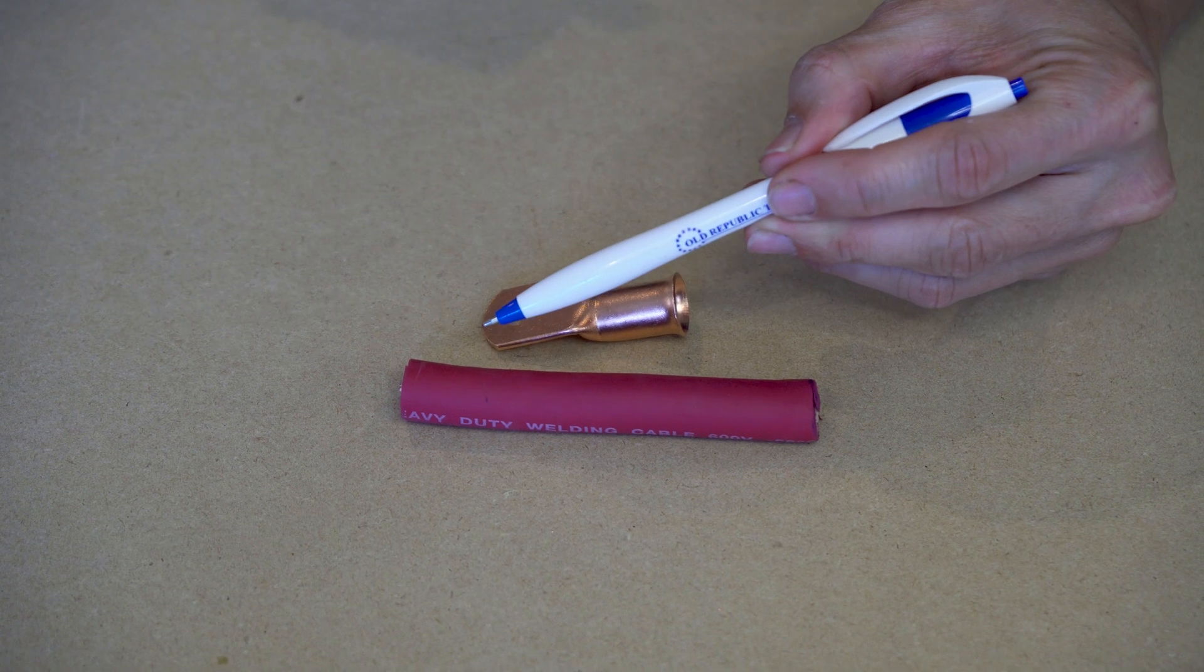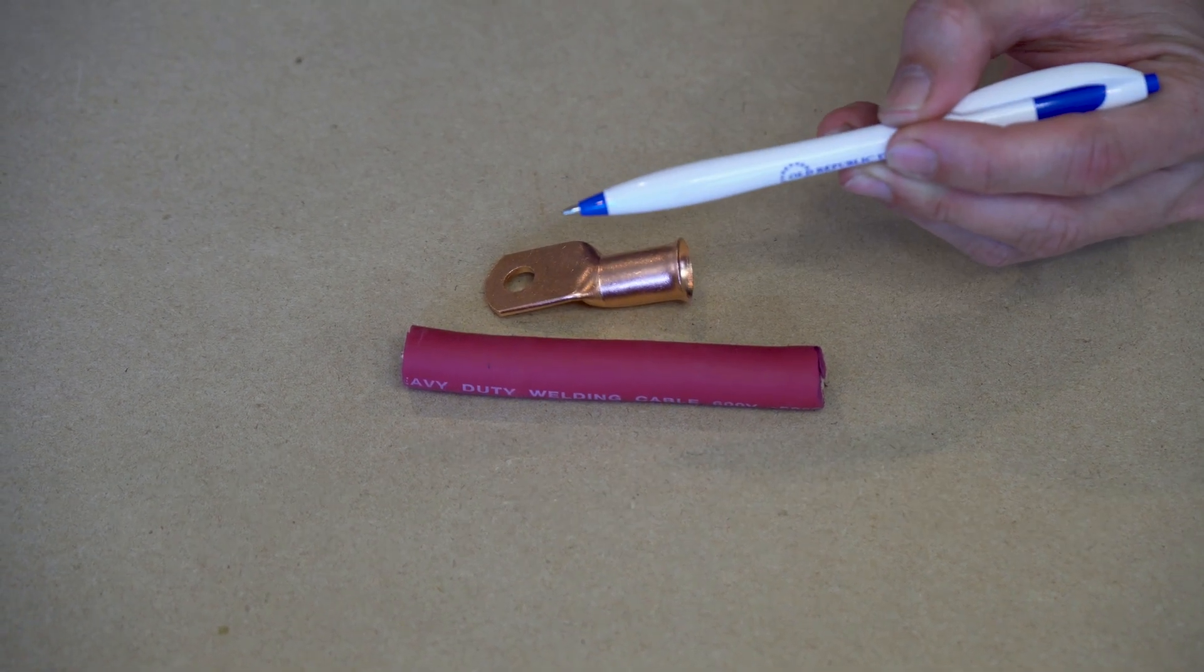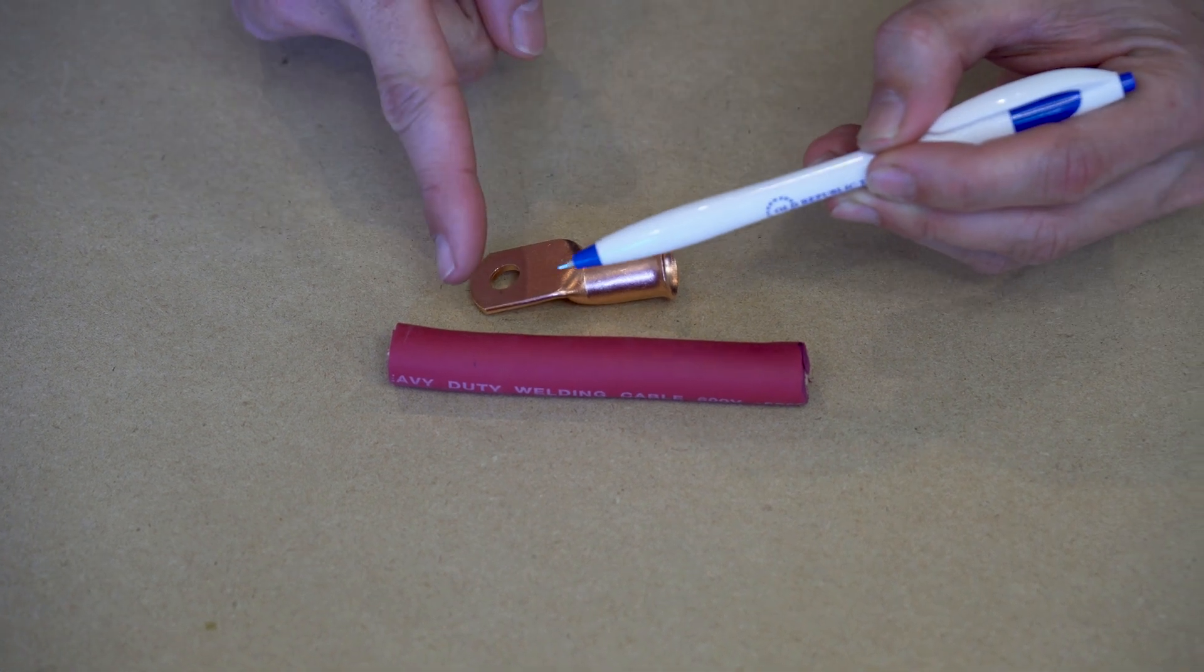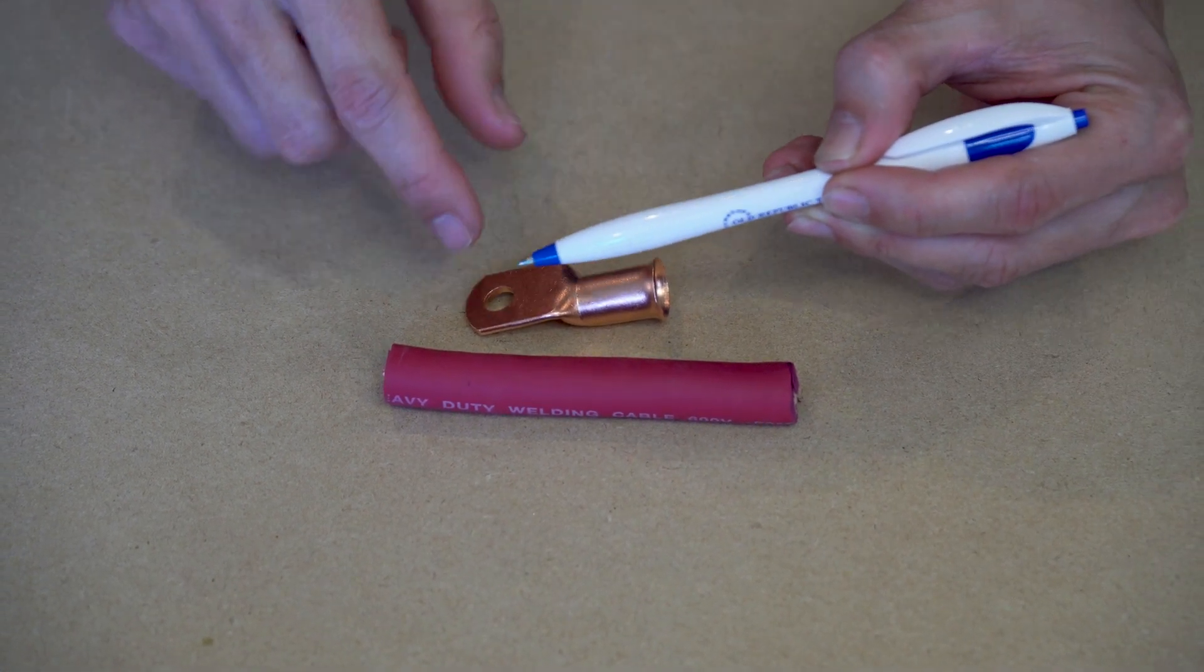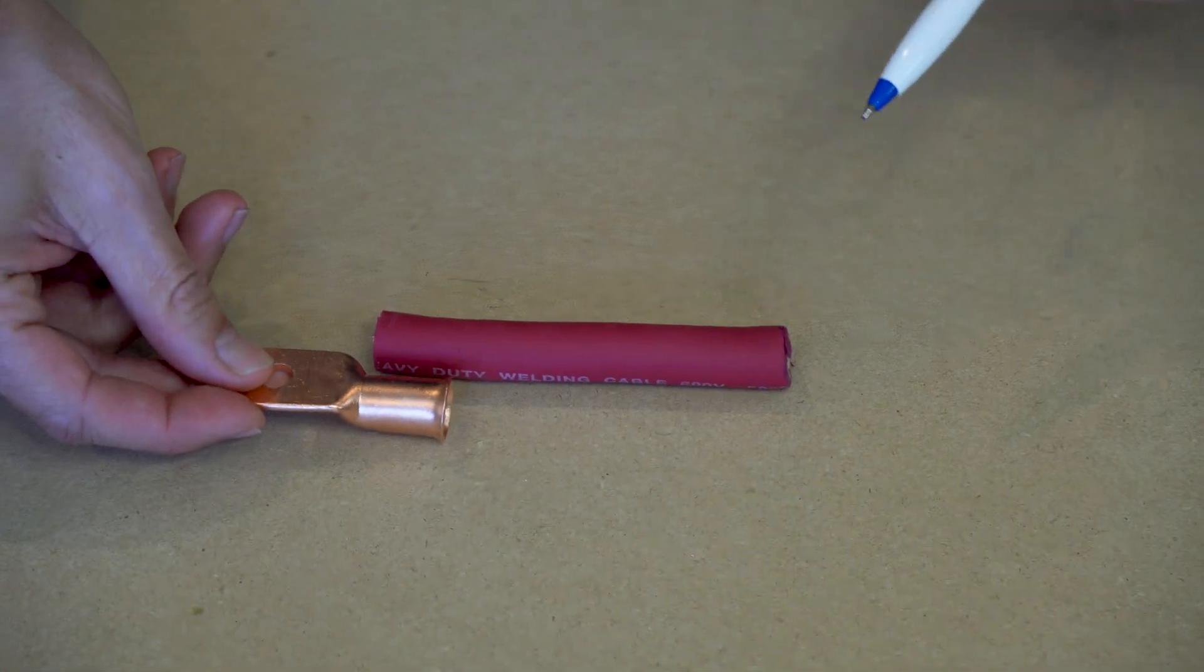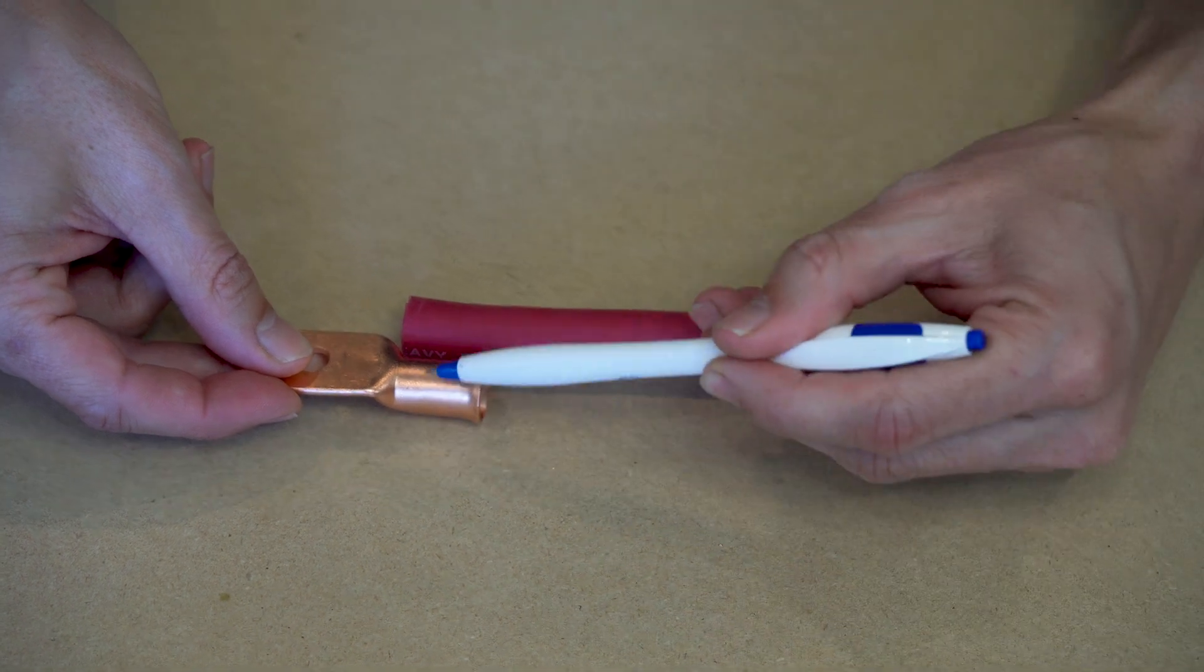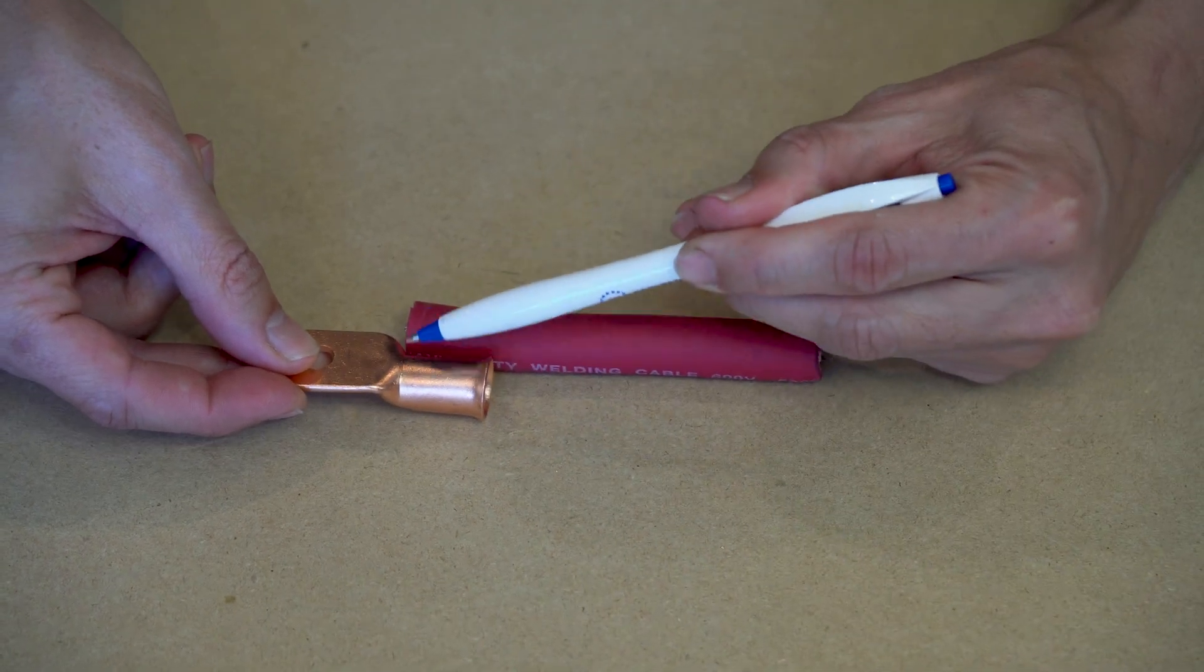Next, we have to cut away the thick insulation jacket to expose the copper conductors. But before you do, you'll want to measure and mark where on the jacket you'll be cutting with this pen. We like to place the wire end side by side next to the lug, with the tip of the wire aligned with the end of the copper barrel, like such.